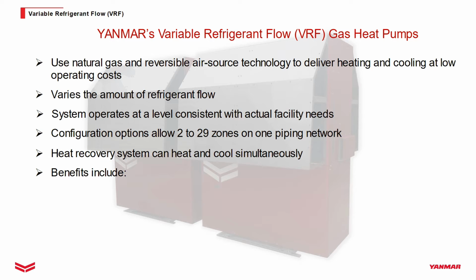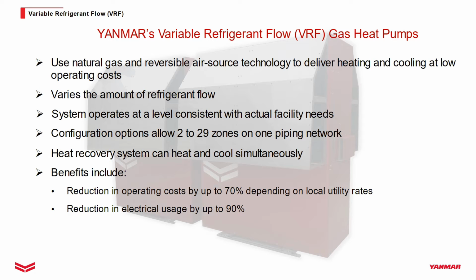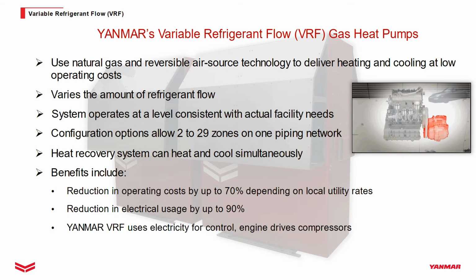The benefits of this system include a reduction of overall operating costs by up to 70%, depending, of course, on local utility rates. A reduction in electricity usage by up to 90%. This reduction is possible because Yanmar's VRF system only uses electricity to energize the control system. The natural gas engine does the heavy work and drives the compressors. Because this system primarily uses natural gas, there is a significant reduction in harmful emissions when compared to other HVAC approaches and lowered system lifecycle costs.